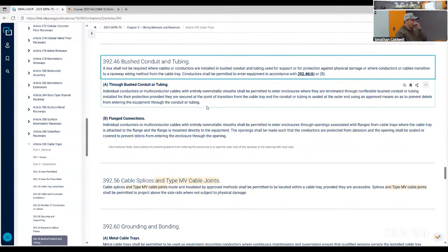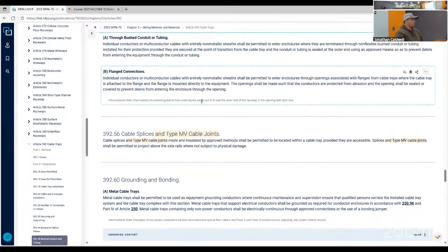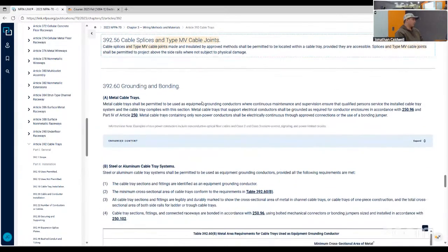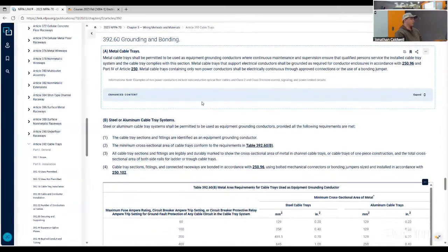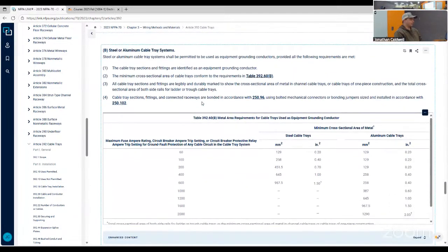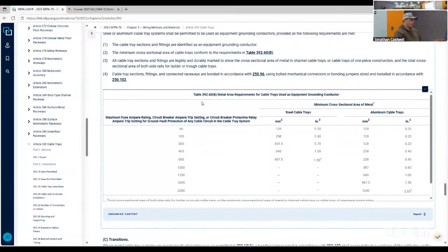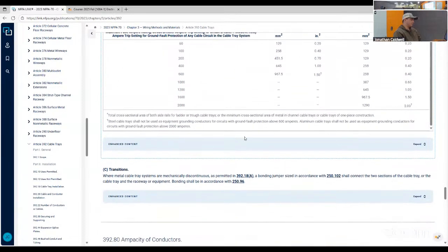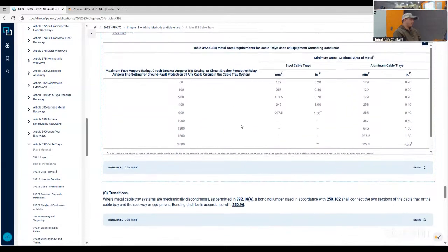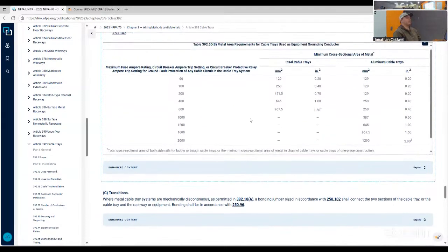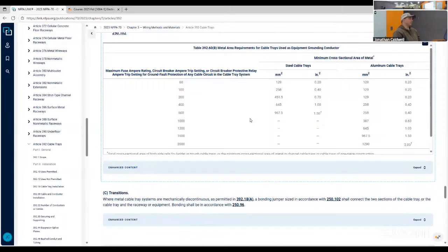Bushed conduit and tubing, just use bushings. And then cable splicing, you can splice some trays. And then it talks about metal cable trays and how you need to ground them, and the minimum equipment grounding conductor and so on. Like I said previously, we only use fiberglass where we work, but we do bond the steel that supports it.